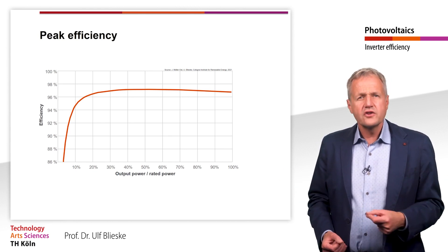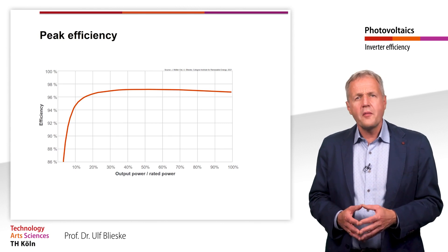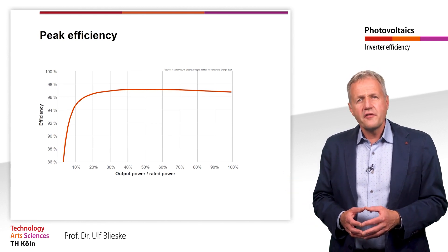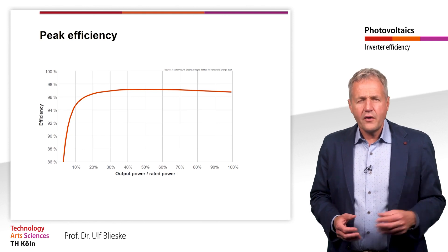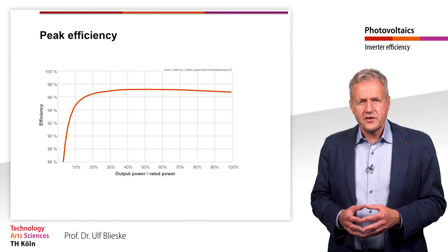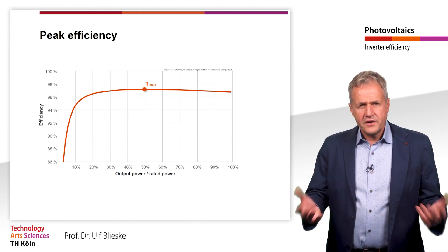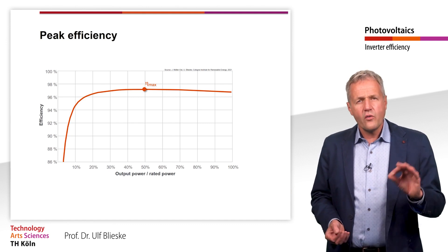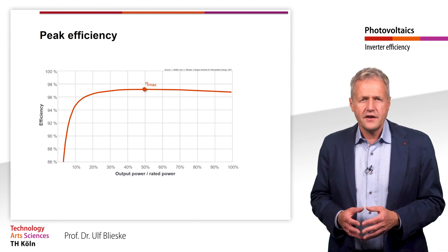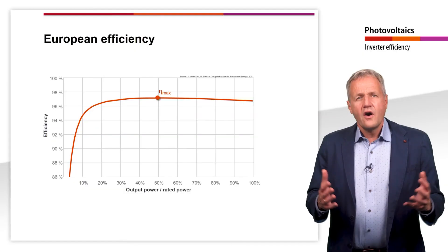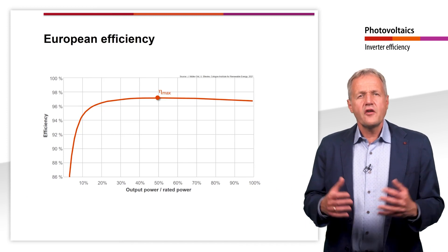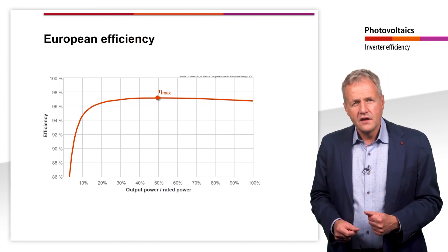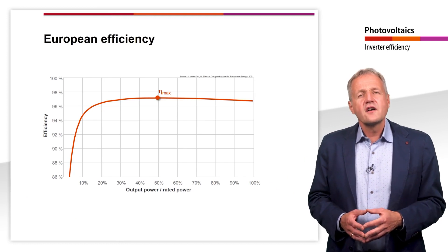Good single-phase transformerless inverters today achieve maximum efficiencies of about 97%. For three-phase devices the efficiency is even about 1 to 1.5% higher. However, peak efficiency is of limited use when comparing inverters.